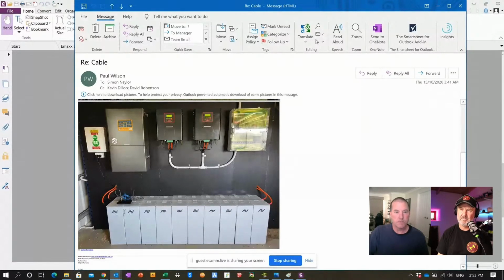Basically, each of the modules is paralleled internally, series connected internally with copper bus bar. This is 1600 amp rated, so 2 rows of 800. You can't see any intercell connections at all, it's all done through internal copper bus bar between the cells. Yeah, it's a copper tube actually, and the balancing wire passes through the tube. So it's all very simple and hidden, meaning you don't have to put a battery enclosure around it because there's no touchable terminals.